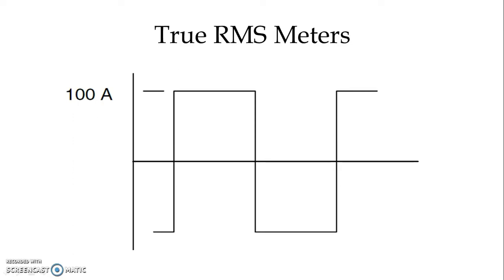An average value reading meter will measure 100 amperes and multiply it by 1.11, giving an RMS value of 111 amperes.